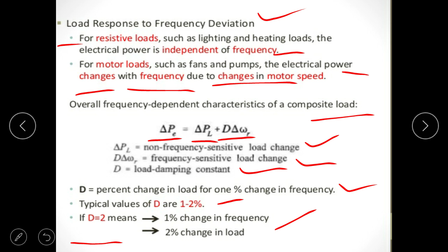So the overall frequency dependent characteristic of a composite load is delta Pe equals delta PL plus D times delta omega r, where delta Pe is the change in electrical power, delta PL is the change in load power, and D is the load damping constant. D times delta omega r is the frequency sensitive load change, and delta PL is the non-frequency sensitive load change. D is known as the percentage change in load for 1% change in frequency. A typical value of D is 1 to 2%. If D equals 2, it means a 1% change in frequency gives a 2% change in load.